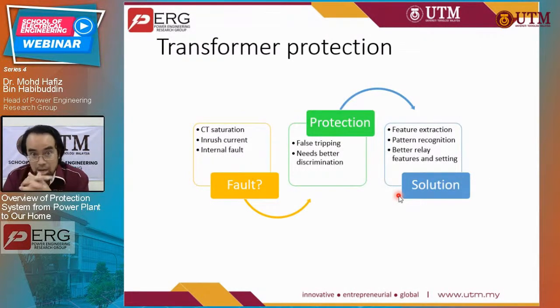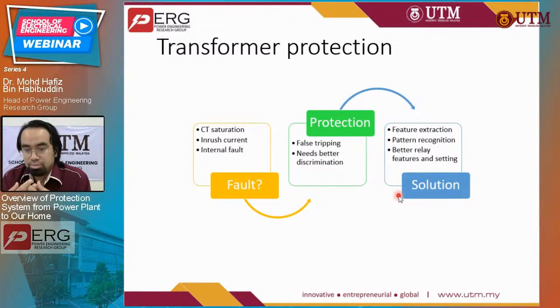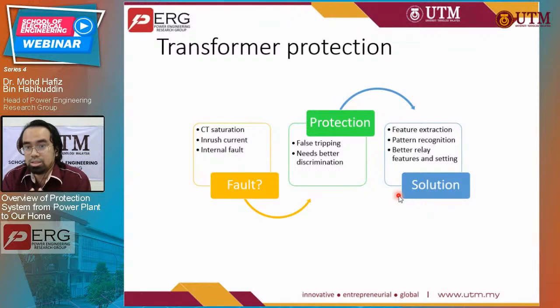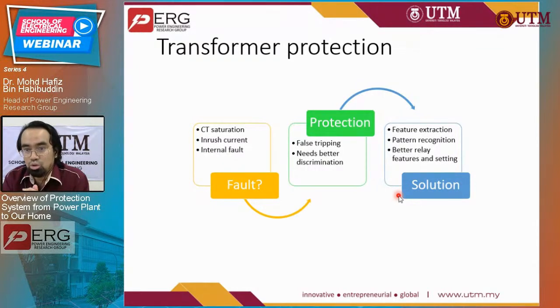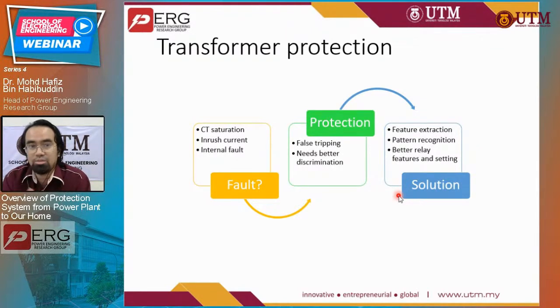What we need is the ability to detect faults correctly. This depends on the equipment being used — first, whether the CT is under saturation or giving accurate readings, and the behavior of the equipment. For example, a transformer has an inrush current of a transient nature, not a fault. We need to decide whether the fault occurs inside or outside the transformer and whether it is truly a faulty condition. You might trip a healthy system due to discrepancies in measurement and operating conditions, so you need better coordination and better discrimination for the relay.